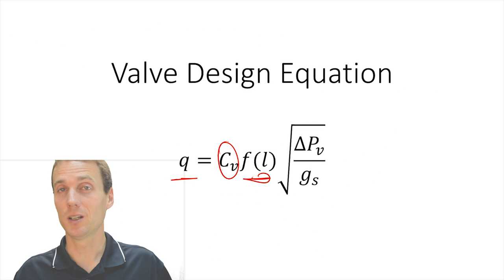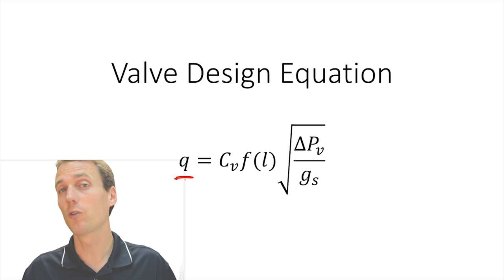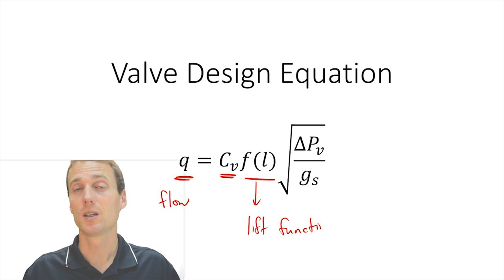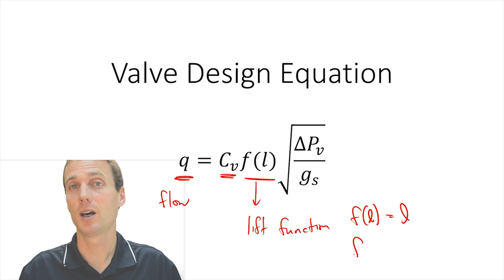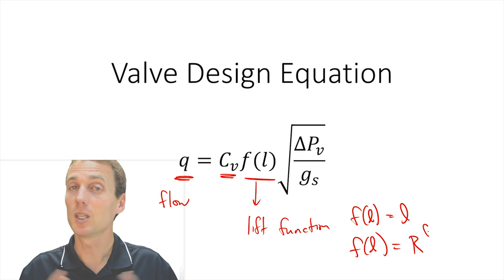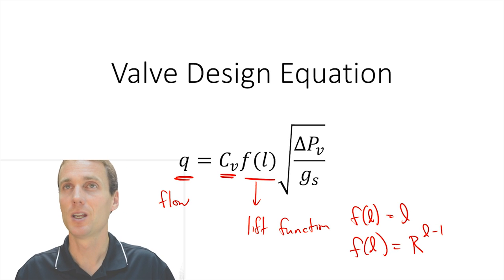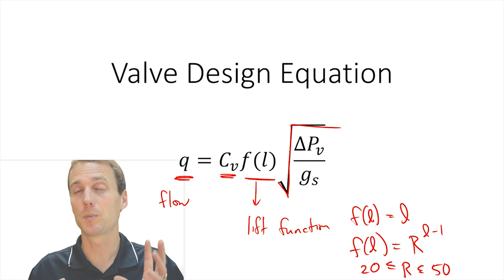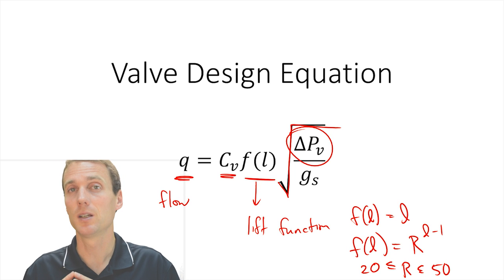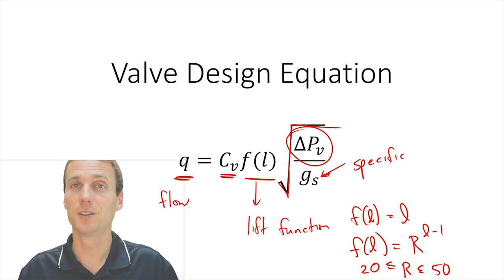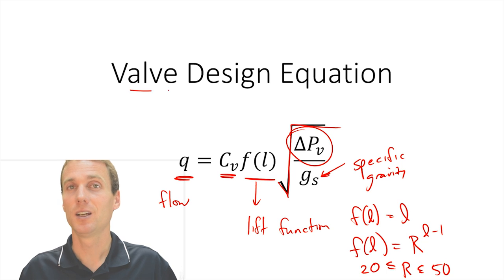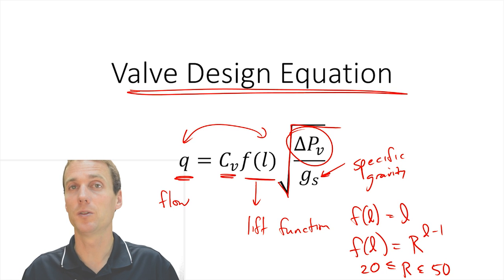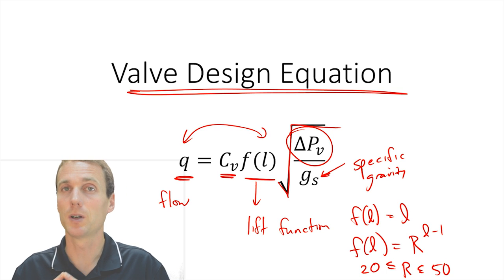Let's go on to the valve design equation. The flow Q is equal to CV times a lift function F(L). If that's a linear valve, F(L) is just lift. We'll also be talking about equal percentage valves, so linear or equal percentage valves. You also have the square root of a ratio: delta PV — the pressure drop across the valve — divided by the specific gravity of the fluid flowing through the valve. This is the valve design equation, and it relates the lift to the flow. If we have constant pressure drop through the valve, then lift and flow are the two variables in the problem.